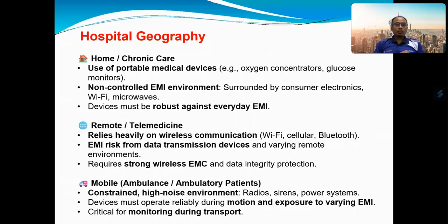Normally, this device is exposed to a high noise environment, and is constrained, such as radios, sirens, and also power systems. All of this kind of medical device must operate reliably during motion and exposure to varying EMI.